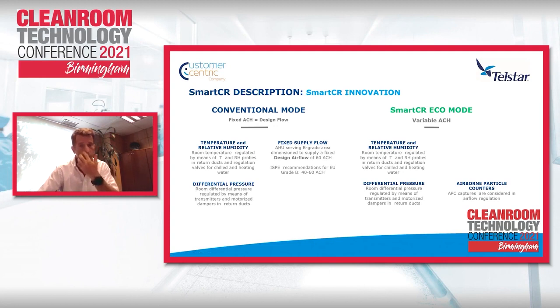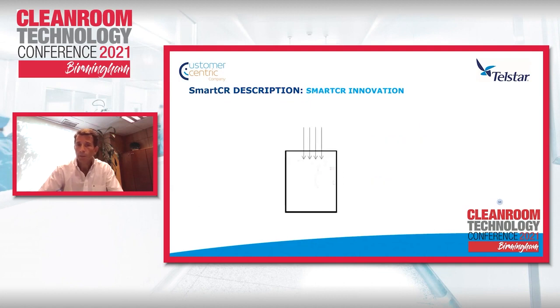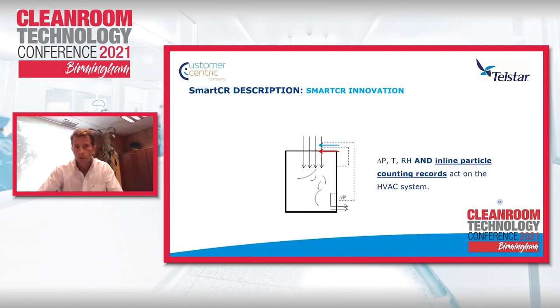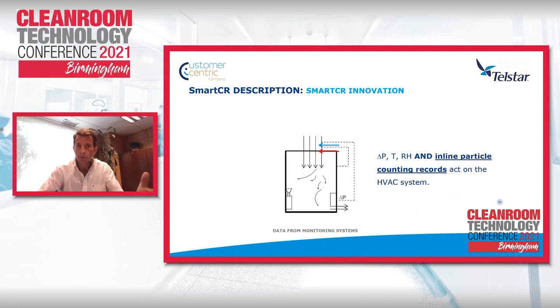airborne particle measurement. So together with the temperature, humidity, and differential pressure data acquired from the clean rooms, we will have the particle counters into consideration. And this will help us adapt the supply air. We can see it in a different picture.